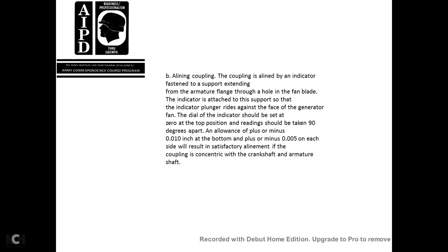The coupling is aligned with an indicator attached to a support extending from the armature flange through the hole of the fan blade. The indicator plunger bears against the face of the generator's fan. The dial of the indicator should be set to 0 at the top position, and readings should be taken at 90 degrees apart. The allowance is plus or minus 10 thousandths of an inch at the bottom and plus or minus 5 thousandths of an inch on each side, resulting in satisfactory alignment if the coupling is concentric with the crankshaft and armature shaft.